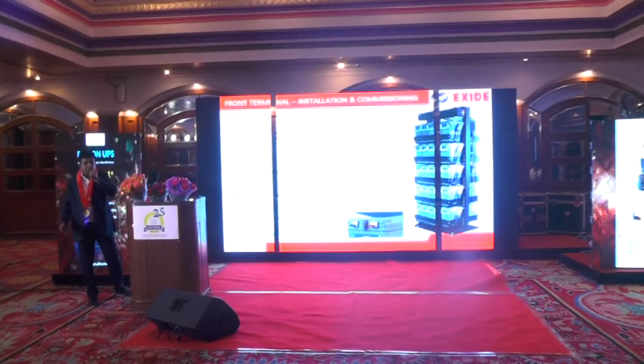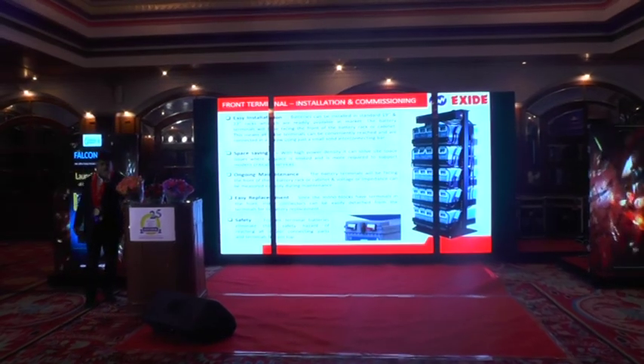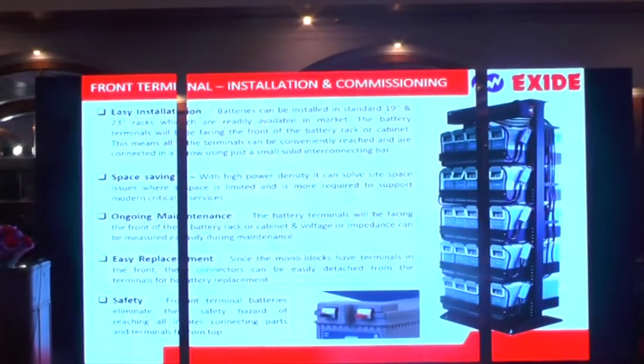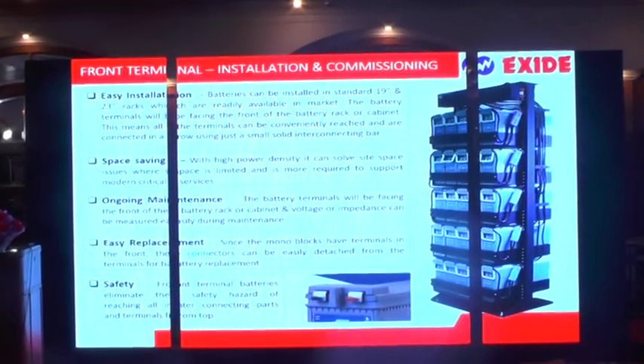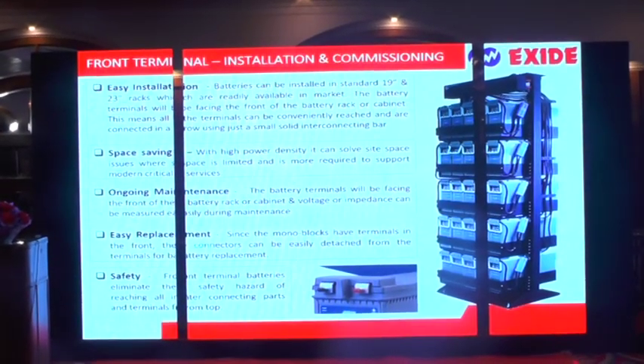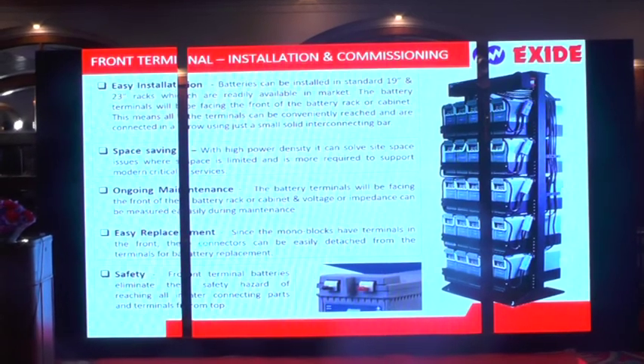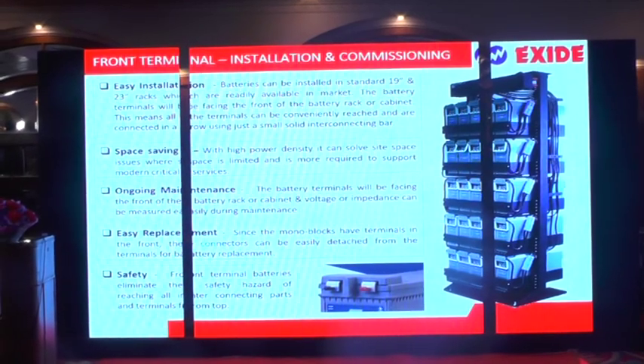This also solves a very important safety issue. Today, in maintaining our UPS batteries, we have to access from the top for connection and disconnection, and there is every possibility of getting a short. When rotating a spanner, if the two terminals are in close proximity, the spanner can short the negative and positive, creating a burst. All of us have experienced bursts in the field. So this is a very important safety aspect regarding this battery installation.